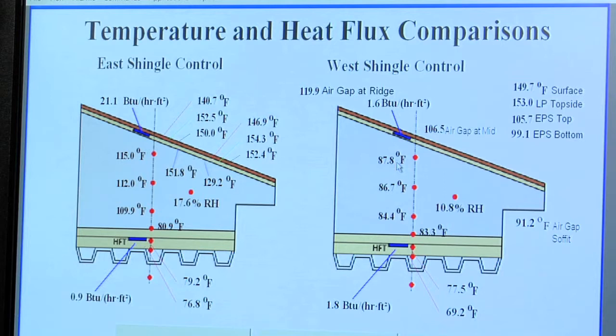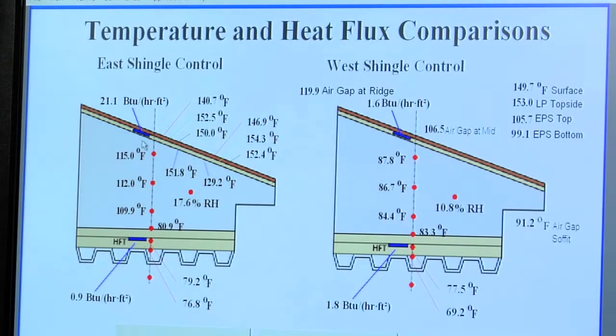The beauty of the ThermaDeck system — as measured by a heat flux transducer — I'm measuring about 1.6 BTUs per hour per square foot heat transfer from the sun entering into the attic plenum. As compared to the conventional shingle roof, I'm measuring 21 BTUs per hour per square foot. That's an indication of how much heat is entering into each respective attic.